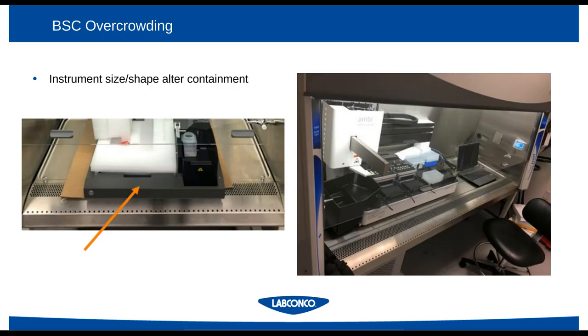To look at this a little bit more closely, here's a couple of examples of some instruments. On the left, there's a liquid handler. On the right, it's an automated bioreactor. And many times, the dimensions of the product will fit within the enclosure, but may block really important parts of biosafety cabinets in particular. On the left, you can see this is the smallest configuration that this instrument allowed, and while it does sit inside the enclosure and can operate functionally without any disruption from the sash, it covers the front airfoil, which means that the biosafety cabinet itself does not have the ability to properly function and contain while keeping samples within the enclosure.